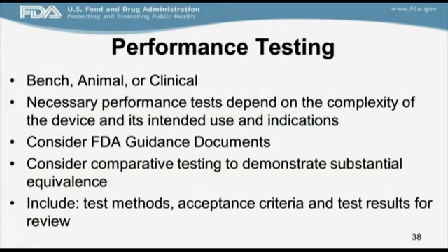I recommend that you consider FDA guidance documents, especially the device-specific guidance documents, which may provide recommendations on appropriate performance testing. You may consider comparative testing to demonstrate substantial equivalence, which could be side-by-side comparison testing of your device compared to the predicate, but that's not required.